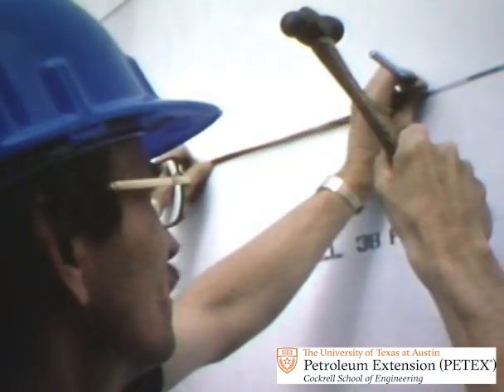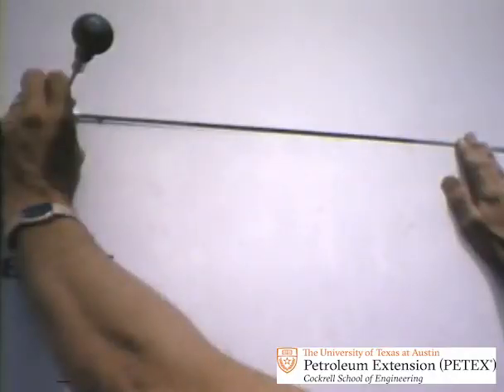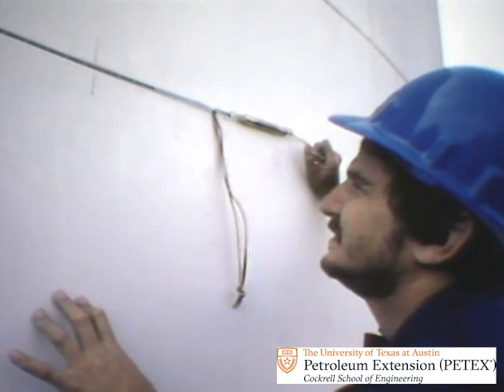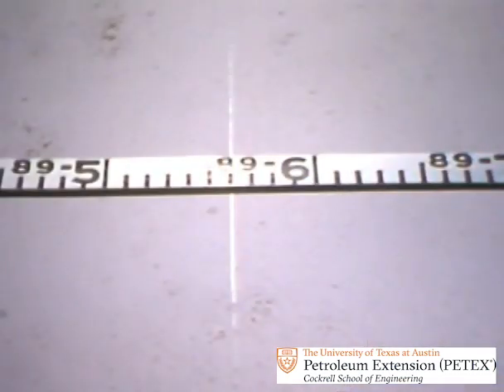They center punch the shell and anchor the standard tape with its zero reading precisely on the 100-foot vertical score. They pull the required tension and read the tape. Since the ring circumference is less than 200 feet, they read where the overlapping standard tape hits the original zero vertical score. In this case, the reading is 89.560. Notice that the tape is marked in tenths and hundredths of a foot. However, the reading is estimated and recorded to the nearest 1/1000th of a foot.